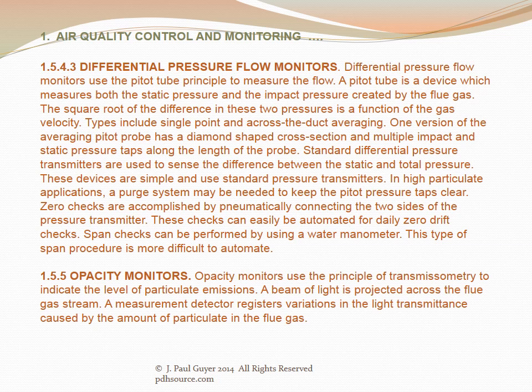Opacity monitors use the principle of transmissometry to indicate the level of particulate emissions. A beam of light is projected across the flue gas stream, and a measurement detector registers variations in light transmittance caused by the amount of particulate in the flue gas.